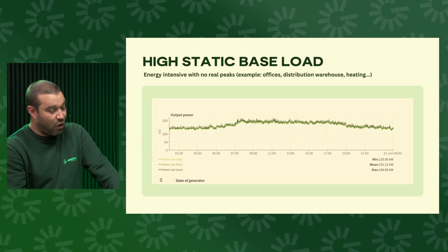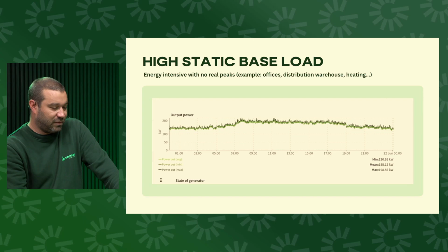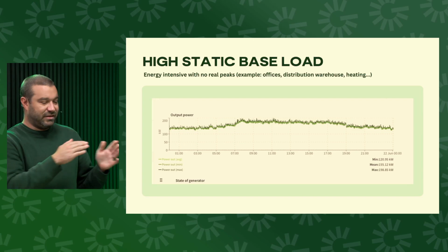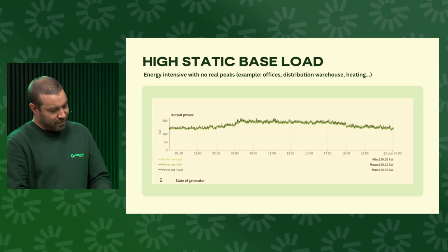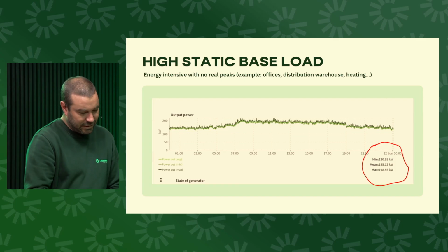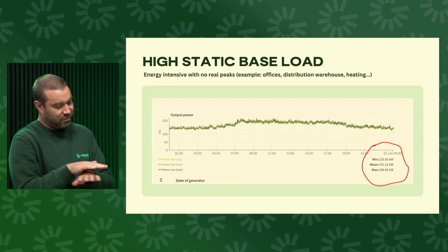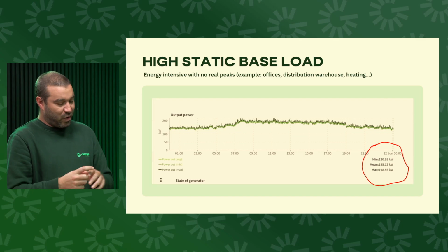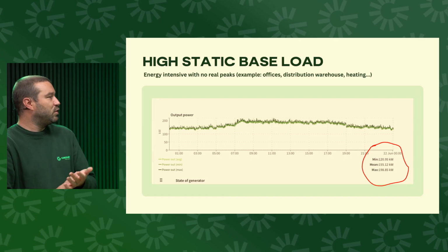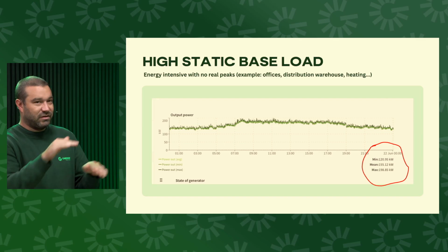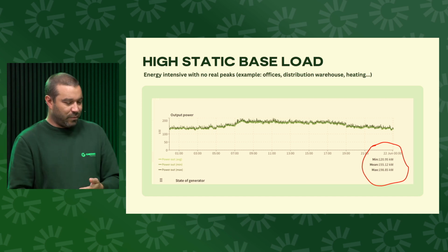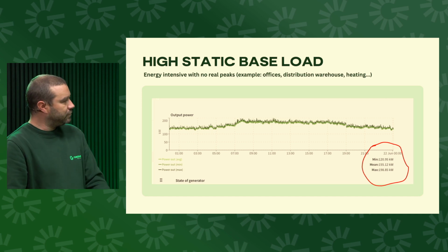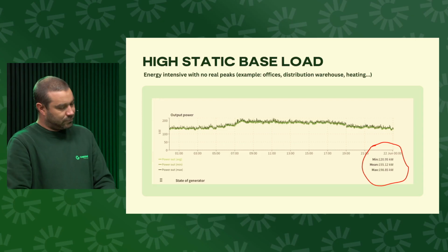So the third area we monitored was the offices or the distribution warehouse, like a heating load, anything like this. It's very constant. There was a slight difference between the minimum and maximum, creating a sort of average mean, but not really something we could do a huge amount with battery storage because it's just a constant load. Not much we can do there, especially compared with the other areas, the business case here is a lot thinner than on the others. Exactly, so that's where we focused our efforts.